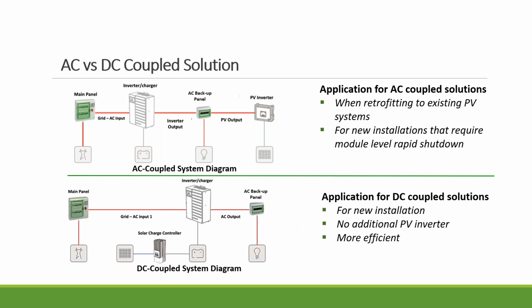Another thing I want to point out is that in the AC coupled system there's one weak point. If the grid goes off, your PV inverter and the hybrid inverter work together to power your home load. If the battery is fully charged and your home consumption is lower than your PV production, now you have a problem, because that excess power has no place to go. What's going to happen is the hybrid inverter will, through a frequency shift, shut the PV inverter off. Then 5 minutes later, the PV inverter comes back again, and they shut off again, come back again. So really, DC coupled is a much better solution. Even if you have old string inverters, like SMA, it's better to replace those string inverters with a DC coupled solution.